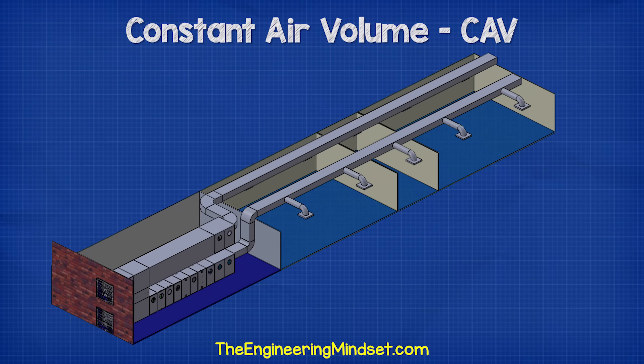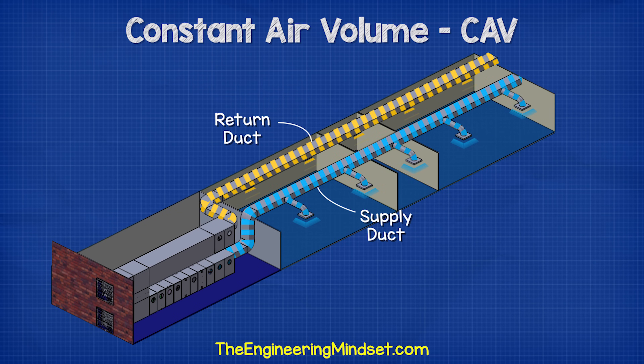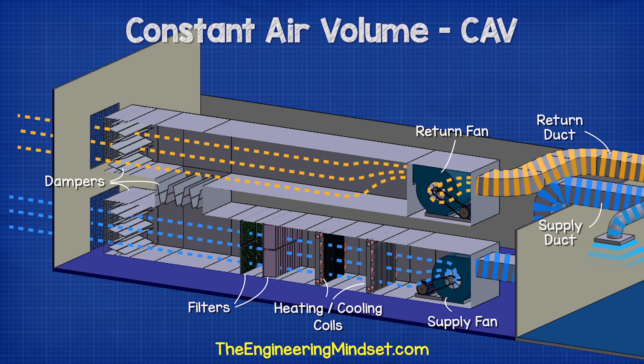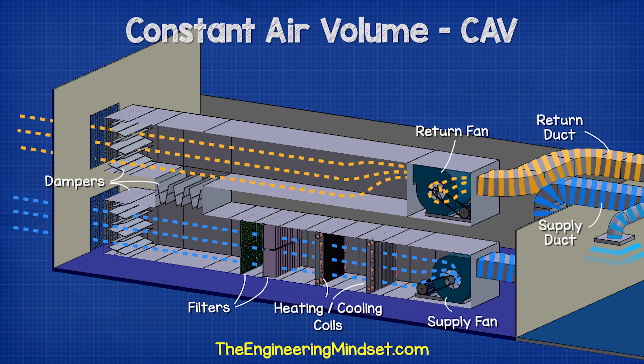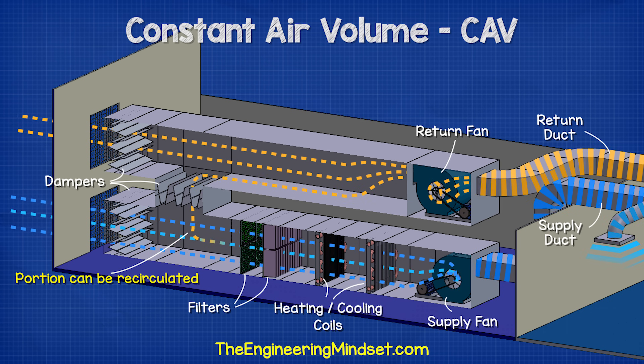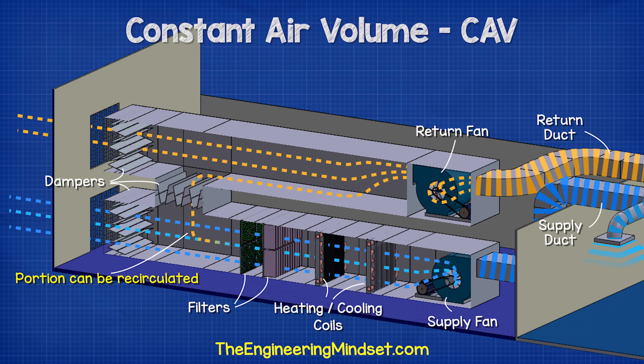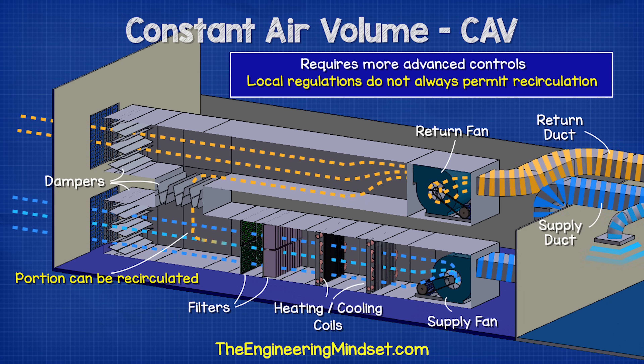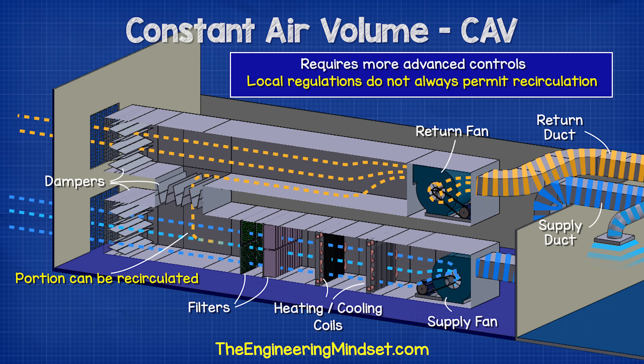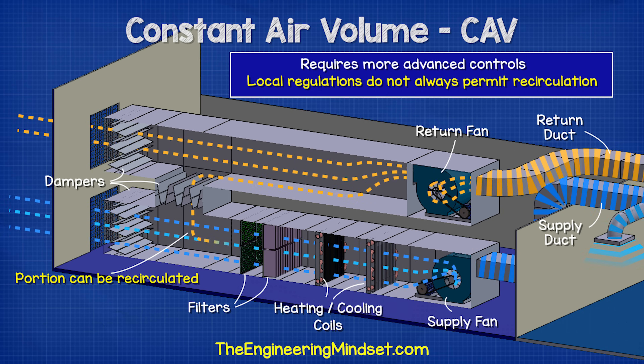The return grill is connected to the main return duct, which runs the length of the building and returns to the AHU. A separate return fan pulls the air in through the grill and brings this back to the main AHU. This dirty used air can then be rejected from the building, although some designs of AHU allow a portion of this air to be recycled back into the supply stream. Recycling a portion of this air will reduce the energy consumption of the system, though this does require more advanced controls and some local regulations do not always permit it.